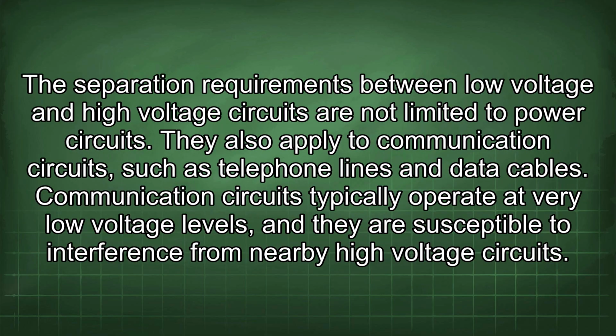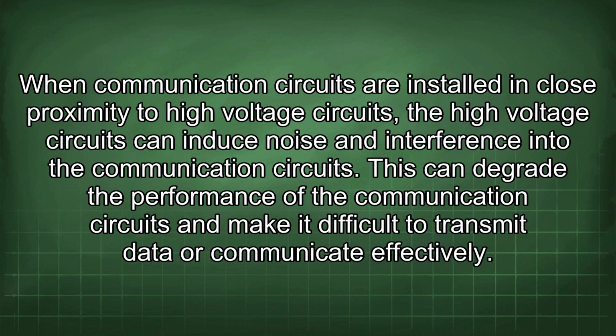The separation requirements between low-voltage and high-voltage circuits are not limited to power circuits. They also apply to communication circuits, such as telephone lines and data cables. Communication circuits typically operate at very low voltage levels, and they are susceptible to interference from nearby high-voltage circuits. When communication circuits are installed in close proximity to high-voltage circuits, the high-voltage circuits can induce noise and interference into the communication circuits.